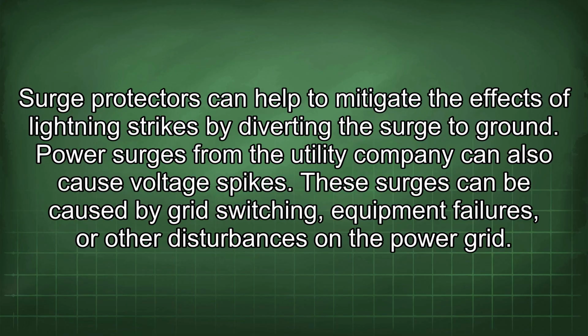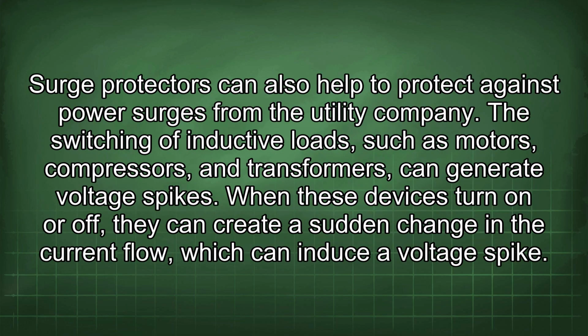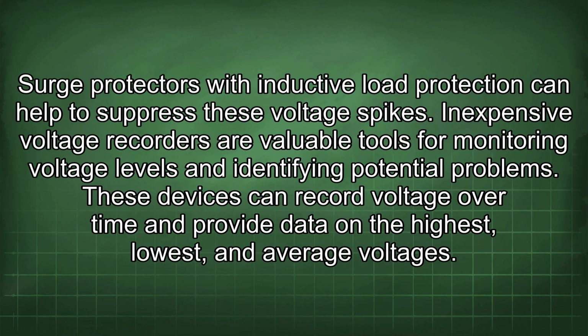These surges can be caused by grid switching, equipment failures, or other disturbances in the power grid. Surge protectors can also help to protect against power surges from the utility company. The switching of inductive loads, such as motors, compressors, and transformers, can generate voltage spikes. When these devices turn on or off, they can create a sudden change in the current flow, which can induce a voltage spike. Surge protectors with inductive load protection can help to suppress these voltage spikes.